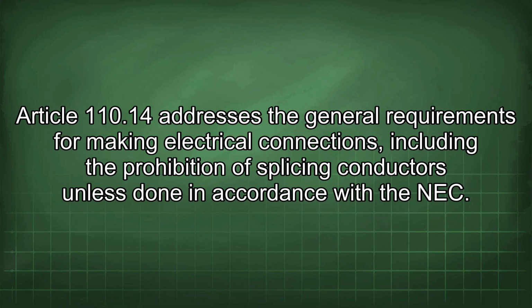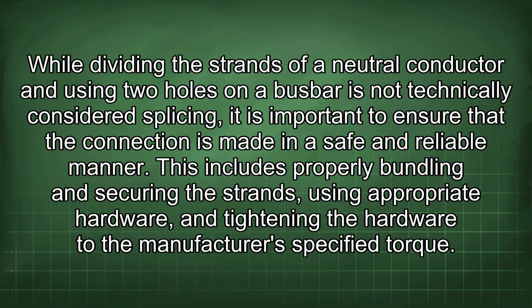Article 110.14 addresses the general requirements for making electrical connections, including the prohibition of splicing conductors unless done in accordance with the NEC. While dividing the strands of a neutral conductor and using two holes on a busbar is not technically considered splicing, it is important to ensure that the connection is made in a safe and reliable manner. This includes properly bundling and securing the strands, using appropriate hardware, and tightening the hardware to the manufacturer's specified torque.